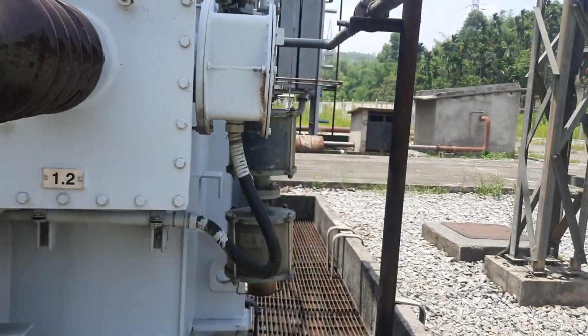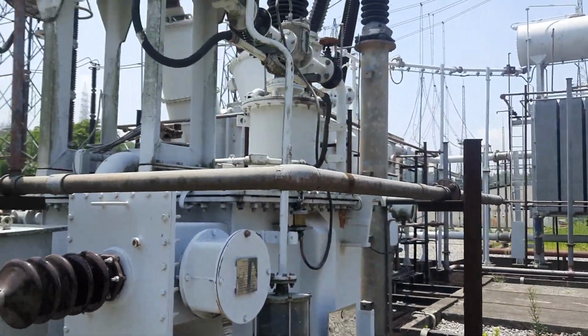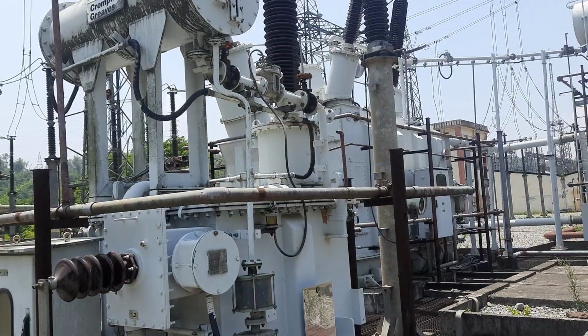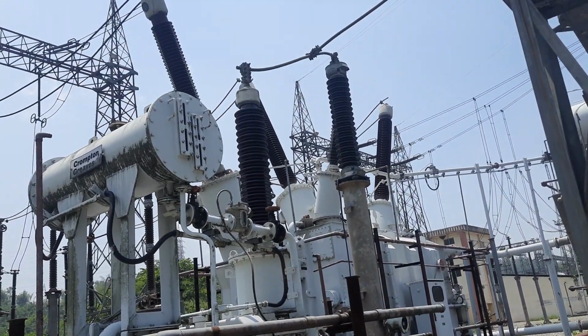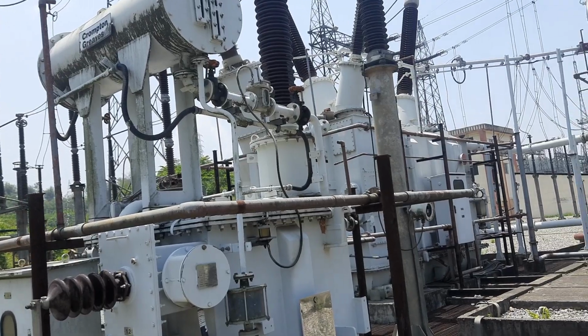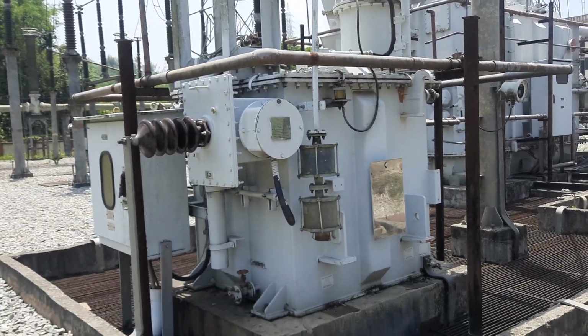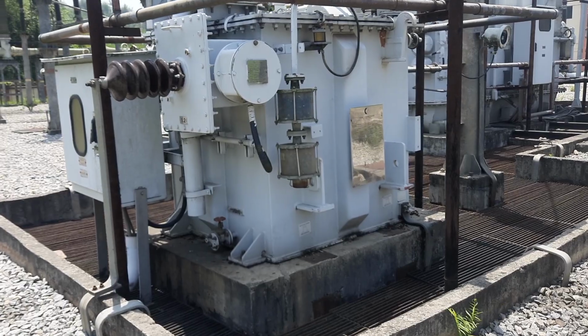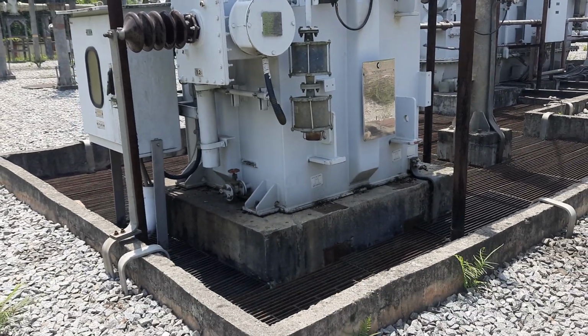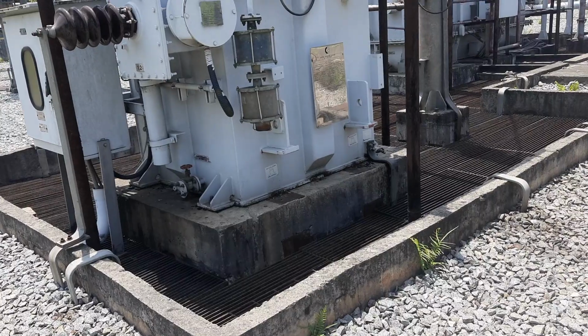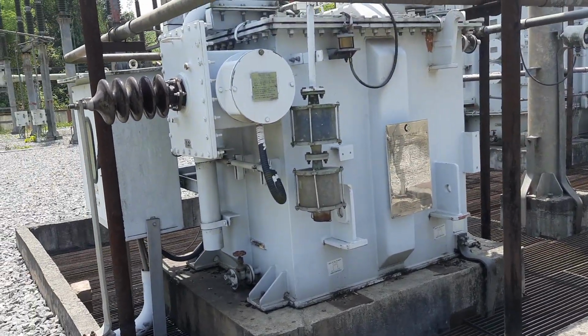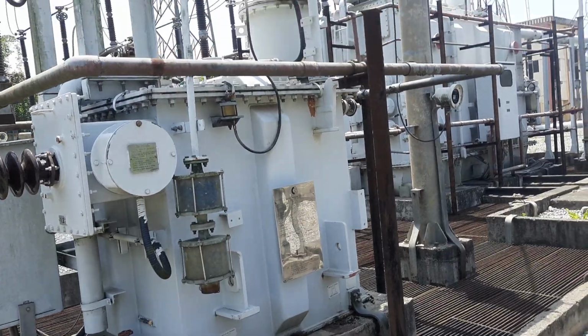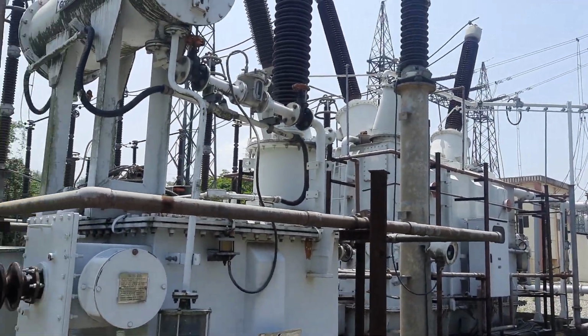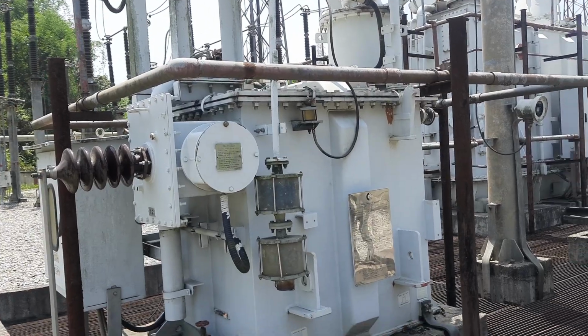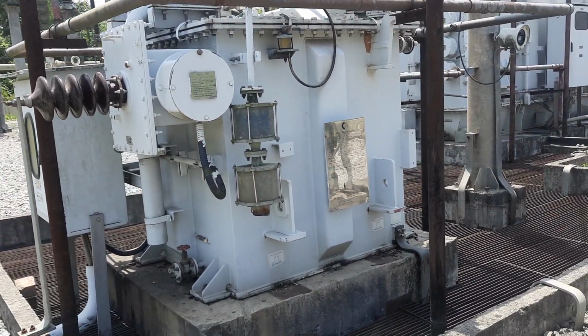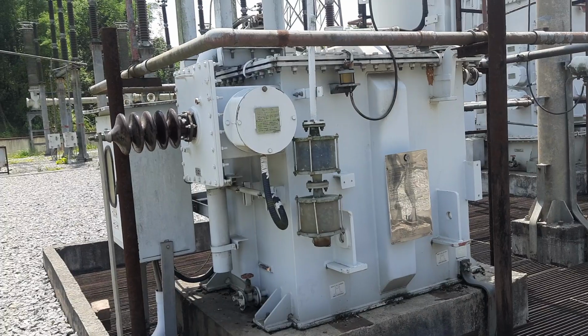This is actually a 145 kV class reactor. That means the bushing that we are using is 145 kV RMS value, and the capacity of this NGR is 40 kVR. It is big enough, because ideally you should have zero current, but practically that is not possible. The rated continuous current allowed to flow through this is 10 ampere, and it is a reactance, an impedance of 400 ohms.